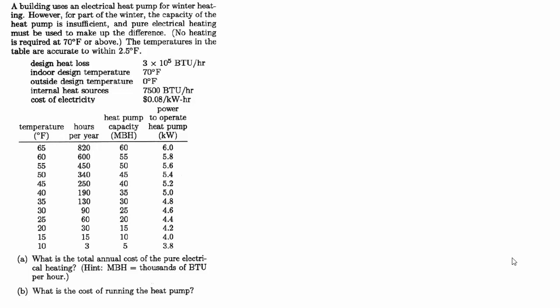We know the design heat loss is 3×10^5 BTU per hour. The indoor design temperature is 70 degrees. The outdoor temperature on a design day is zero degrees. There are internal heat sources of 7500 BTUs per hour total. And the cost of electricity is eight cents per kilowatt hour. And we've been given a table with different temperatures in five degree increments and the number of hours per year that the conditions outside are at that temperature.